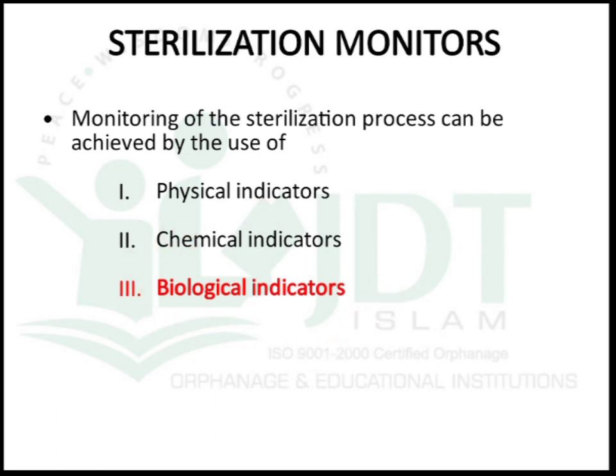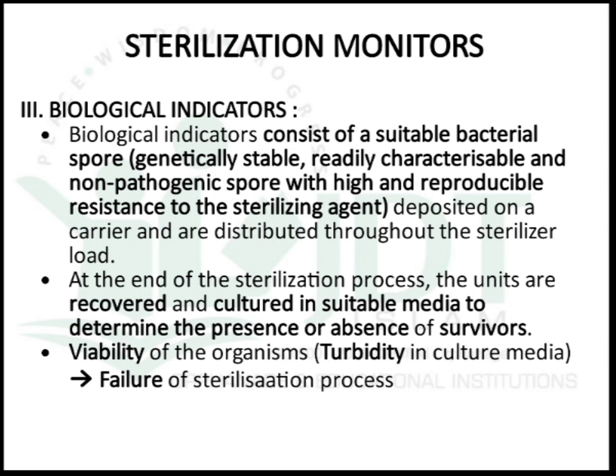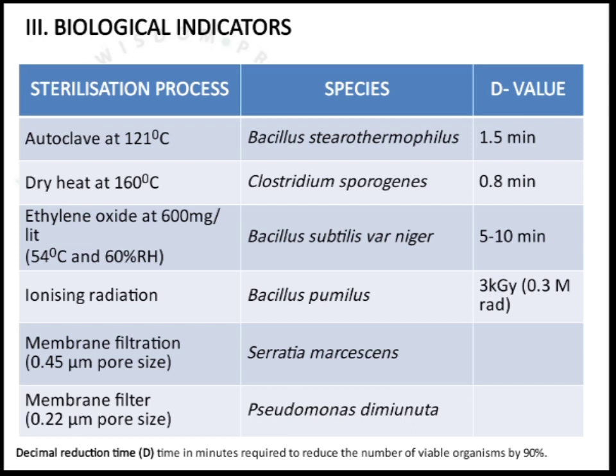Biological indicators used for sterilization monitoring consist of suitable bacterial spores that are genetically stable, readily characterizable, non-pathogenic, and with high and reproducible resistance towards the sterilizing agent. The indicator is deposited on a carrier and distributed through the sterilization load. At the end of the process, the units are recovered and cultured in suitable culture media and incubated to determine presence or absence of survival. Turbidity in the culture media indicates presence of viable microorganisms and failure of the sterilization process.